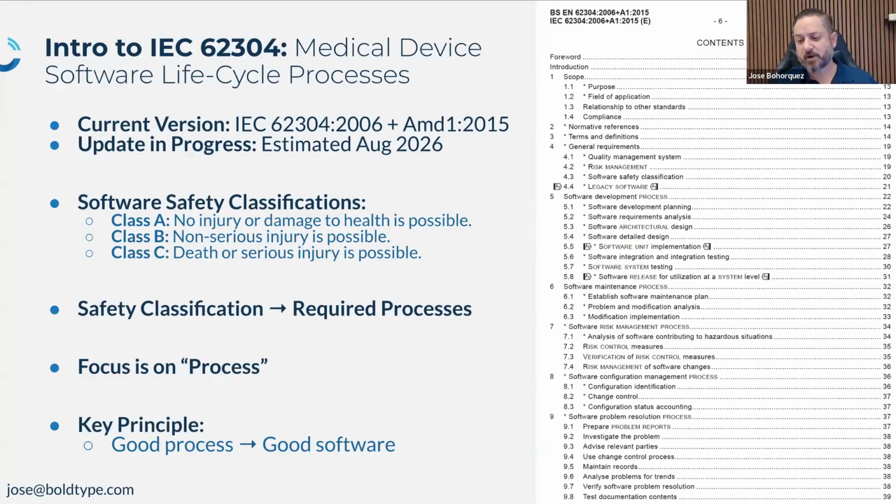Something else that trips people up is they're used to hearing that their medical device is either class 1, class 2, or class 3. Then they get to 62304 and see that their software is either class A, B, or C. Then they fill out their eSTAR form and say the software is basic or enhanced. The simple answer: forget class 1, 2, 3. There's not a one-to-one mapping. Obviously there's correlation. If you're a class 3 medical device with software, it's more likely you're going to be class C, but it's not one-to-one.